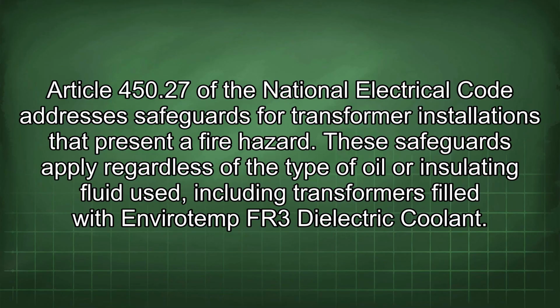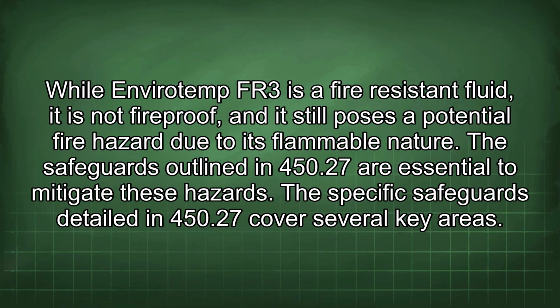450.27 of the National Electrical Code addresses safeguards for transformer installations that present a fire hazard. These safeguards apply regardless of the type of oil or insulating fluid used, including transformers filled with Envirotemp FR3 dielectric coolant. While Envirotemp FR3 is a fire-resistant fluid, it is not fireproof and it still poses a potential fire hazard due to its flammable nature. The safeguards outlined in 450.27 are essential to mitigate these hazards.